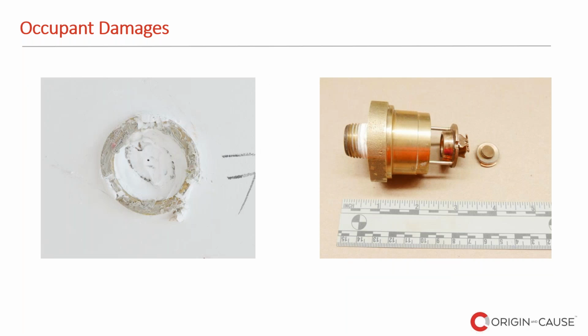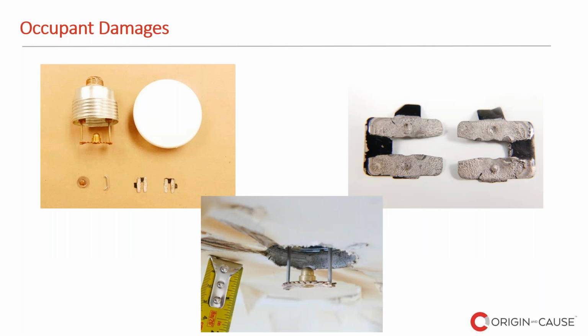Again, these are examples of my investigations where an occupant damaged the sprinkler head. In this case, the occupant put some putty or some drywall compound in the head, the concealed head. This was very interesting because it wasn't only one head, it was all the heads in that apartment unit. And there were obviously some big issues raised in that case.